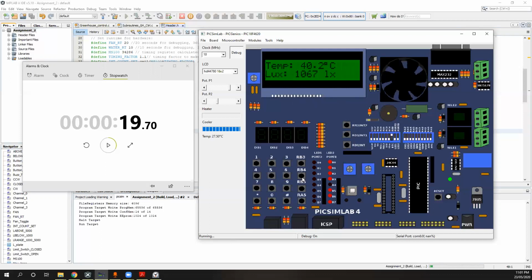After this, I'll show you the buzzer can be turned off by just dropping below the 40 degree set point, as opposed to pressing the button. We've already tested the button for turning off the buzzer at the top end. We'll just drop back through the temperature. Yeah, see that? Just do that again. Yeah, see, buzzer turned off. So you can trigger it on and off two separate ways. Okay, so just set it back to the standard range again. So requirement 5 is done.